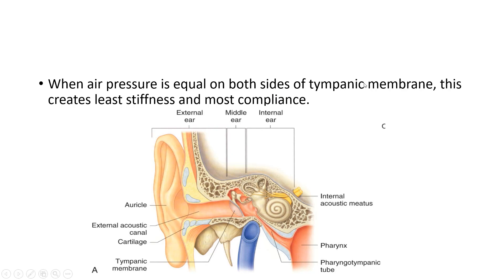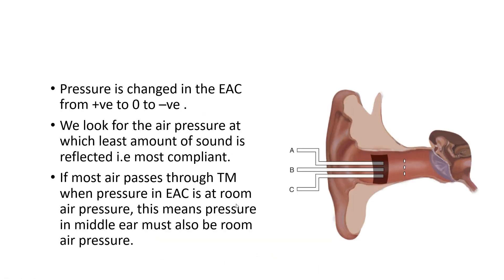When air pressure is equal on both sides of the tympanic membrane — that is on the external auditory canal and the middle ear cavity — this creates the least stiff tympanic membrane. At that point, the tympanic membrane is least stiff and most compliant. Compliance is the inverse of resistance, meaning the tympanic membrane captures or absorbs the most amount of sound and then transmits it. When the pressure in the external auditory canal is any greater or lesser than the pressure in the middle ear, the tympanic membrane becomes stiff. Based on this principle, we use tympanometry to create a tympanogram.